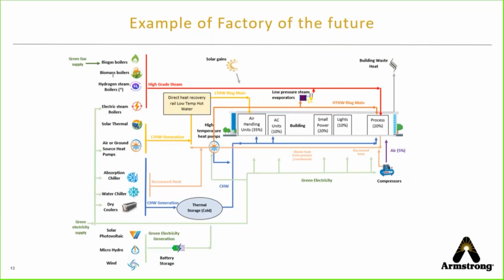We're going to take those heat loads and put those back into the system through heat pumps. We'll take the steam, the high-grade heat off of our processes, combine that with recovered heat from our chillers, take that into industrial high-temperature heat pumps to raise that temperature above the pinch, to deliver that hot water up to 248 degrees Fahrenheit into our network, to take care of 80% of those heating needs that are low-grade heating needs.